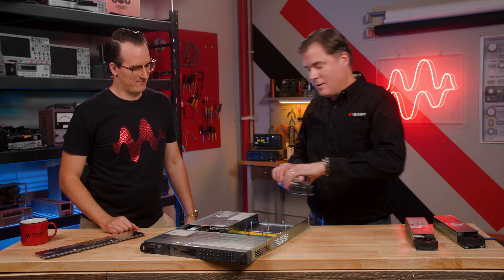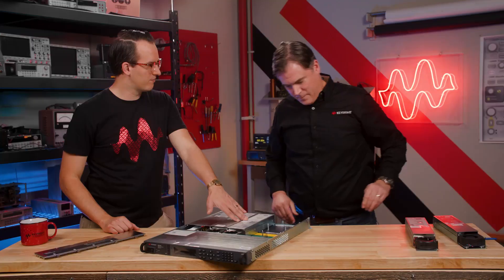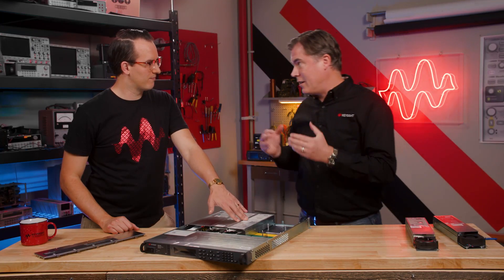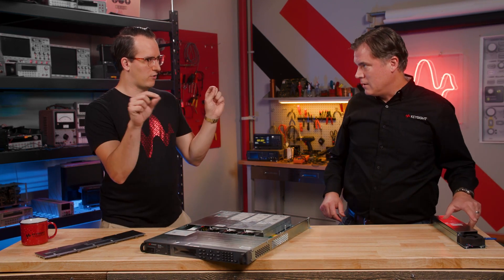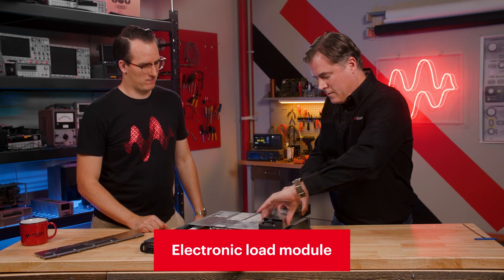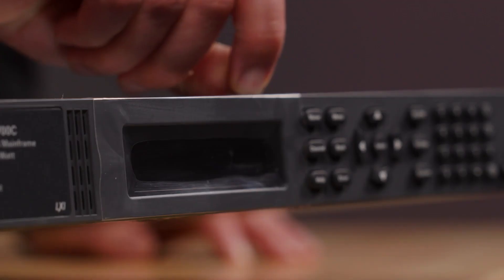So now we're installing a high performance auto-ranging module — that's a normal power supply, but it's really focused on enhanced throughput. And then we have the N6762A precision module — precise measurement capabilities for voltage and current to a high degree of precision. And now we have an electronic load that we can install — so a big fancy resistor, basically. So we're loaded up, we've got the plate in. Are we ready to put it in a rack? Almost — got one last important thing to do.